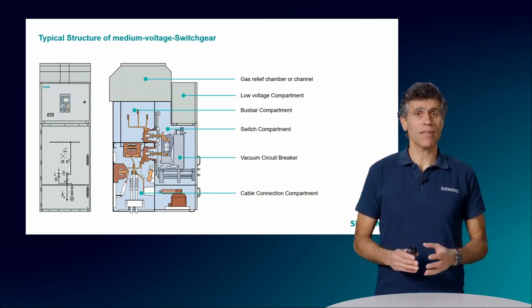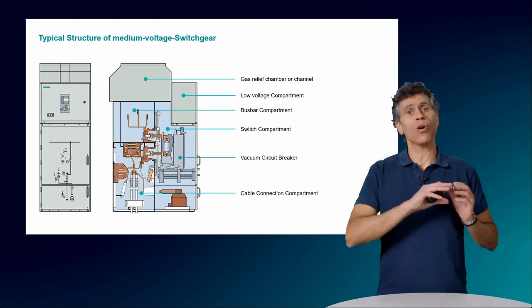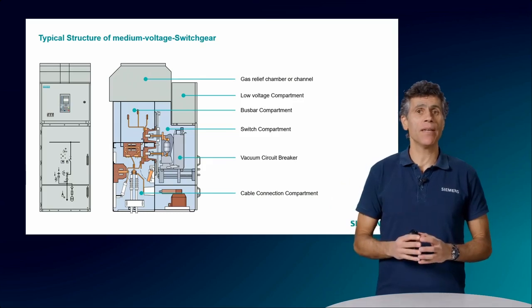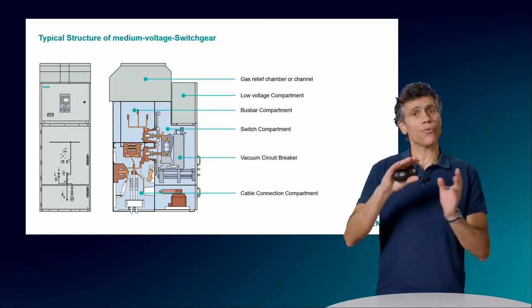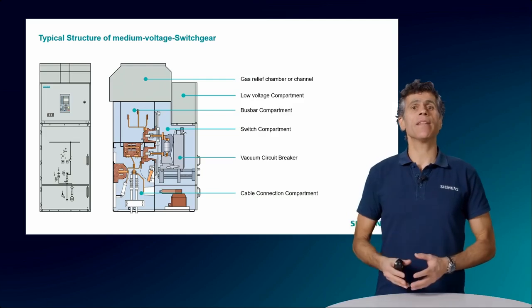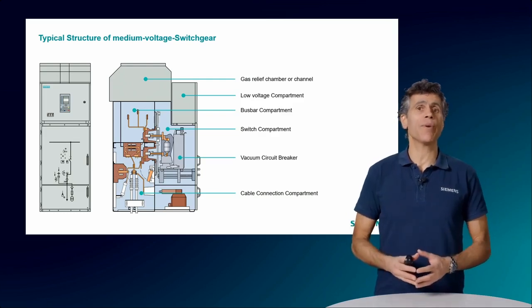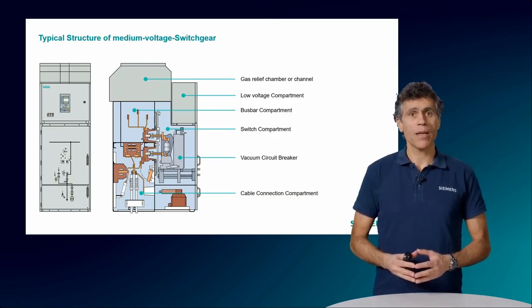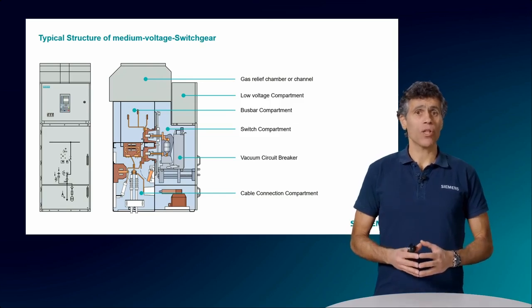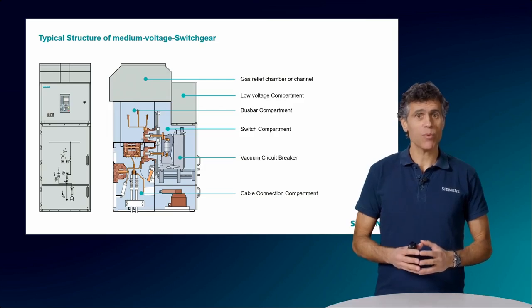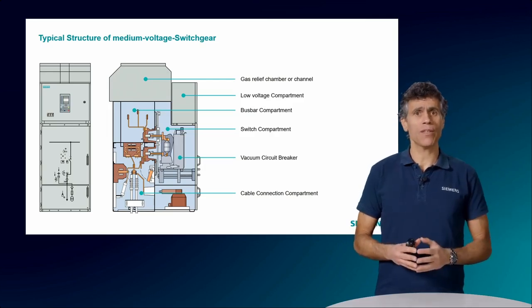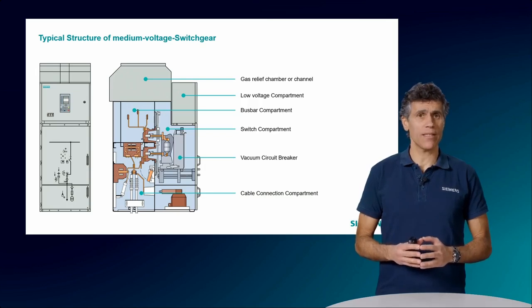The current comes inside the switchgear via one panel, which brings current to the whole switchgear via the busbar, and in each feeder it flows through the breaker into the cables that are connected to a consumer that requires electrical power. Then we have the low voltage compartment, which I usually call the brain of the switchgear. This is where all cables lead to and all sensors are connected to. We will have a more detailed look at this later.